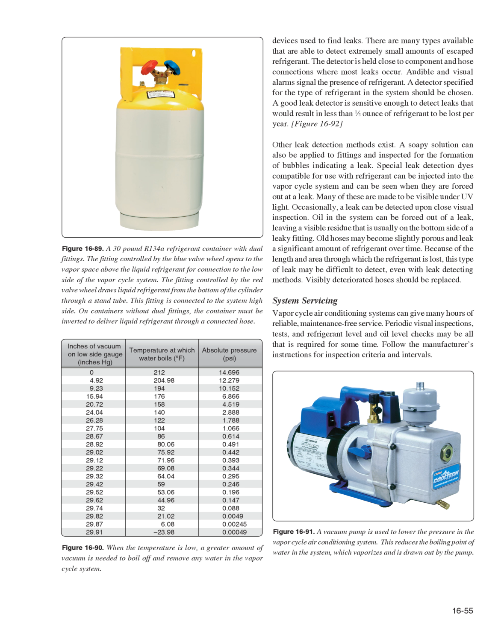Figure 16-92, other leak detection methods exist. A soapy solution can also be applied to fittings and inspected for the formation of bubbles indicating a leak. Special leak detection dyes compatible for use with refrigerant can be injected into the vapor cycle system and can be seen when they are forced out at a leak. Many of these are made to be visible under UV light.